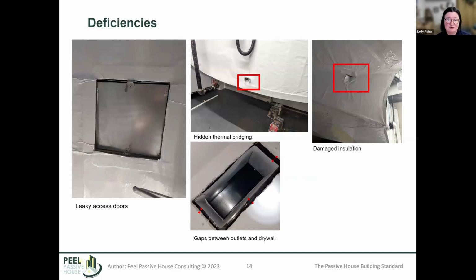So in addition to issues that come from leakages or different filters and components and accessories, we also have a lot of other kinds of deficiencies that come up. If you're measuring your airflow through your ducts, or rather out through an outlet, and you've got gaps to your drywall or wherever it's coming through into your spaces, these gaps can incur additional leakage that you may not realize, because when you're trying to get the air into the space, in some cases it will go in behind these little openings that are never sealed.